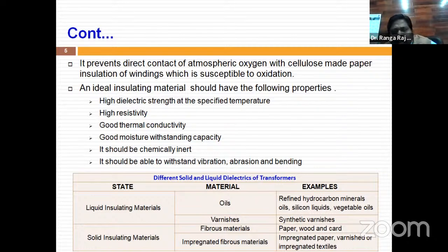If you talk about oils, there are different types - varnishes as well as oils, refined oil, silicone oil, ester oils. There are many oils we can use in transformers. But from an economical point of view, we generally prefer mineral oil since it is cheaper and gives the best operating performance compared to other oils. However, a lot of research is going on in this area, and we'll come to notice these trends by the end of the session.